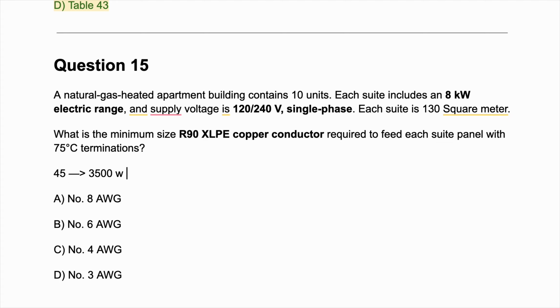For the next 45 square meters we need to assume 1,500 watt, and for each next 90 square meters we need 1,000 watt.